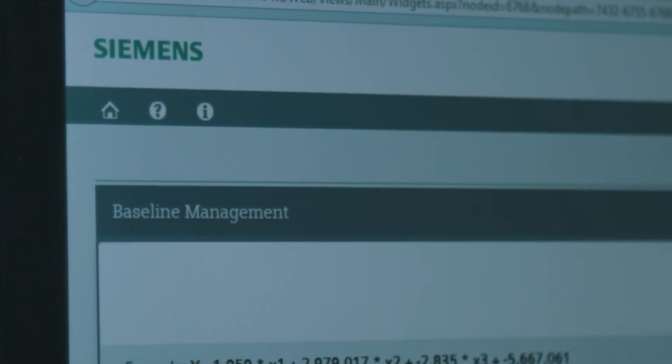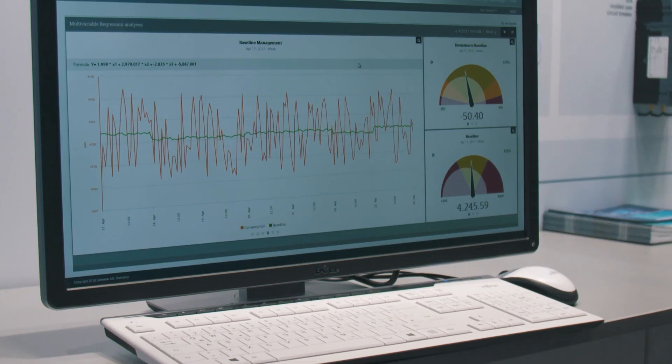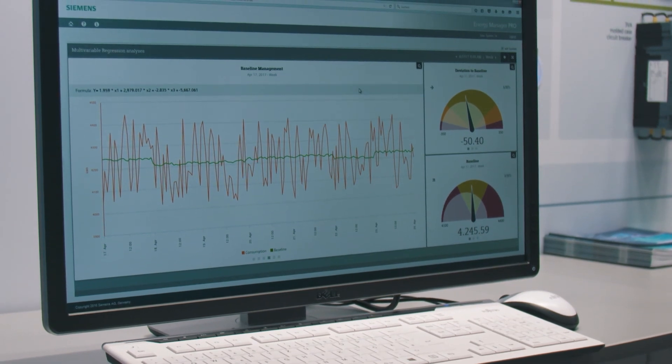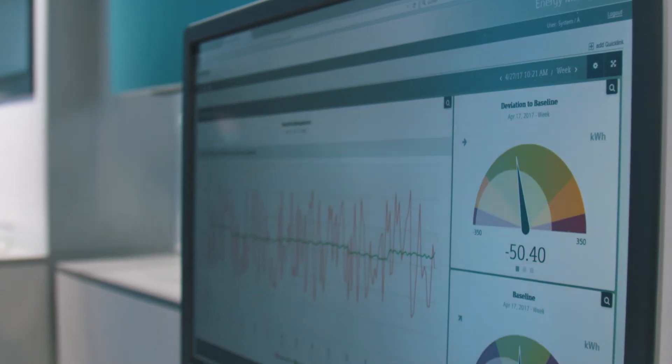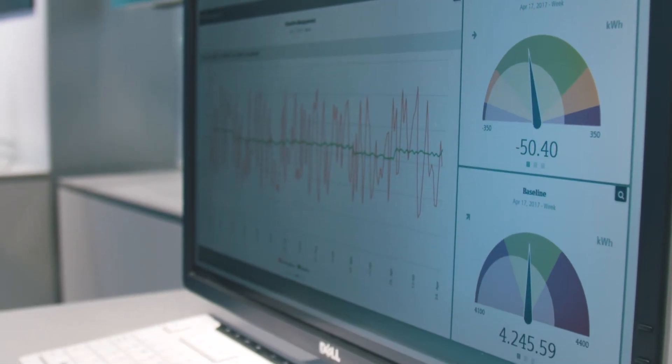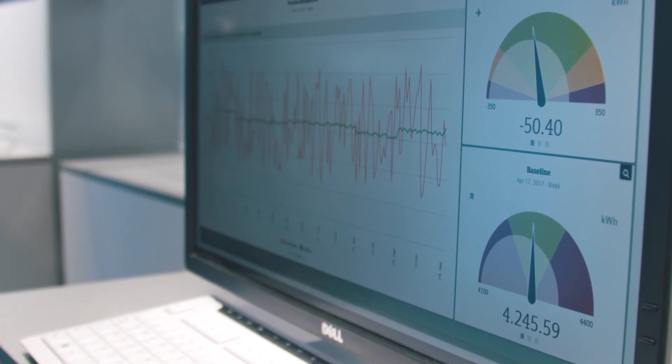The energy consumption of plants often depends on several influencing factors like production volume or outside temperature, and these rigid limits hinder simple monitoring. The baseline management of SIMATIC Energy Manager Pro now allows for calculating a dynamic limit value — the reference value — taking into account these influencing factors. This information is then visualized in the web dashboard for the user, and due to deviations from the baseline, he can identify whether the plant has deteriorated under these specific framework conditions.